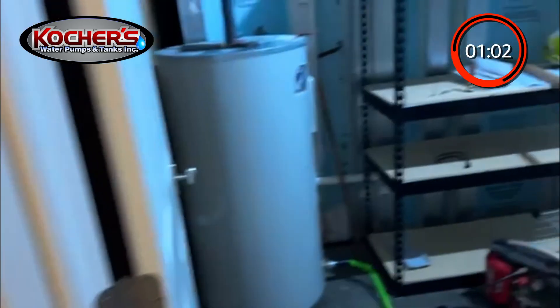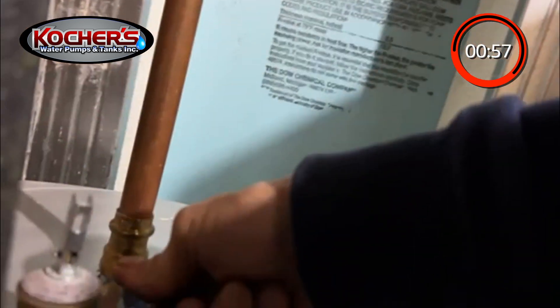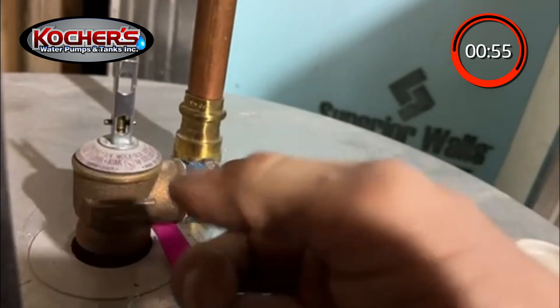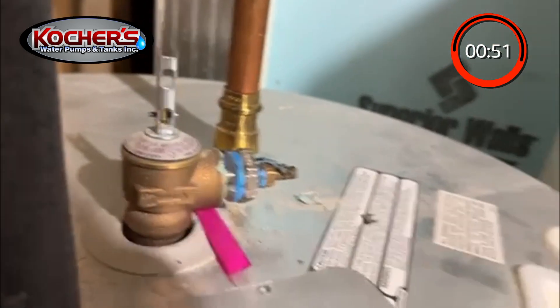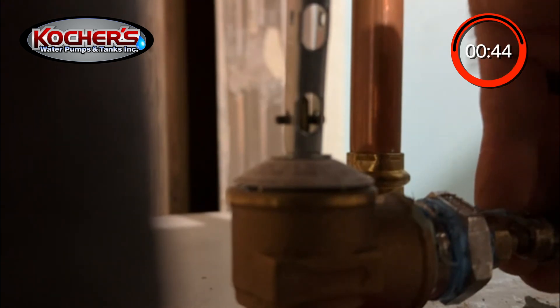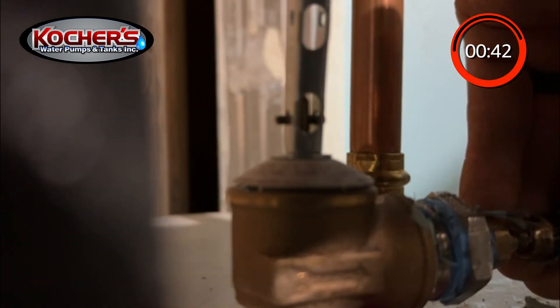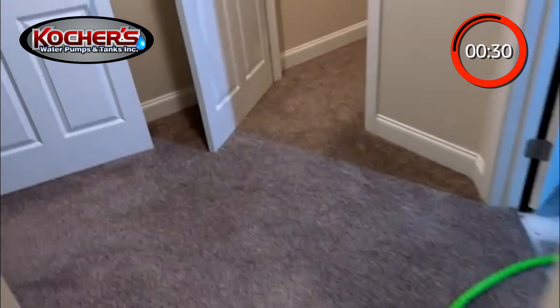What I'm going to do is put this air fitting — a Schrader fitting — in the water heater, and I cracked the pressure-relief valve open. Now all you do is keep putting air into the water heater as it drains.